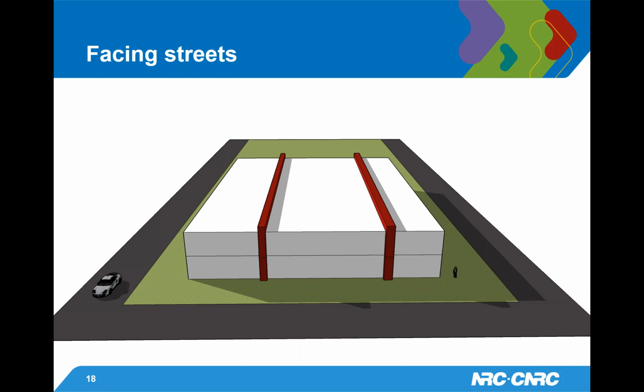What does that mean? Now take this picture as an example. Larger buildings subdivided by firewalls will need to meet the 25% perimeter rule. In this case, the building in the middle would not conform to the new 25% rule, while the other two would. So the middle building would not be permitted to be constructed using the new mid-rise combustible construction requirements. This new provision has a significant impact on infill projects in urban areas, where street access on the side of a building is not always possible. So there's a recent proposed change to address this concern. We will discuss it in part 2 of the presentation.